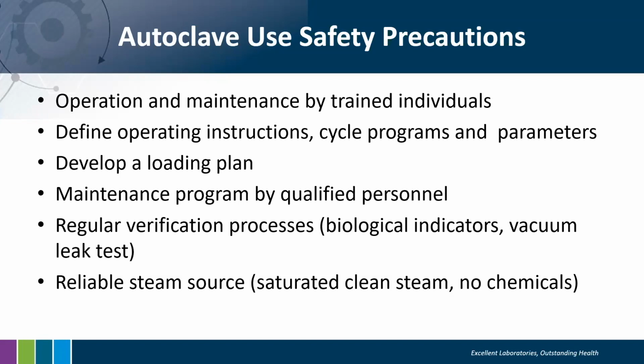Develop a loading plan. Imagine that if you have everything crammed inside the autoclave, there is no space for the steam to circulate and get in contact with everything inside. So having a loading plan and a method of how the waste is going to be placed inside the autoclave is really important. The maintenance program needs to be done by qualified personnel, and there are tests used to measure the amount of steam in the autoclave and all the parameters to make sure the autoclave is working properly. Of course, there are regular verification processes, and for that there are indicators that can be used, such as the biological indicator. We'll talk a little bit more about that in a minute. And vacuum leak tests for autoclaves as well.